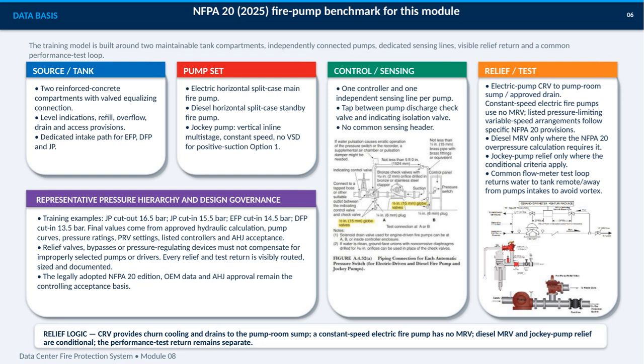The electric pump's churn relief drains to the pump room sump or an approved drain, while diesel and jockey pump relief are conditional. The shared flow meter return goes back to the tank away from pump intakes. Pressure examples are training values only. Final settings depend on calculations, equipment data, pressure ratings, and AHJ approval.